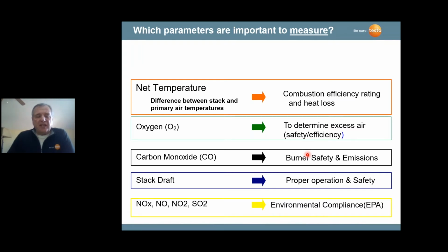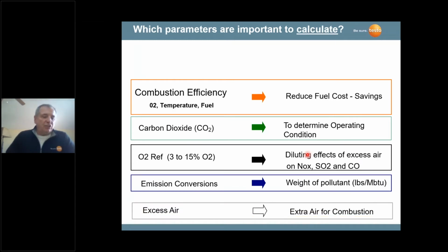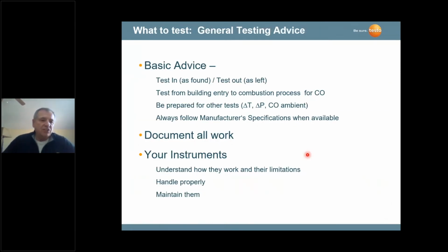Here are the measurements that we measure: net stack temperature, oxygen, carbon monoxide, draft. All these are sensors that go into an analyzer. We do the calculations too. We can measure oxygen and temperature and know the fuel, and we can calculate the combustion efficiency. We can calculate carbon dioxide and other emission values as well. So when using a combustion analyzer, test in, test out. Always check carbon monoxide in the area of the combustion process. Document your work. Most of these instruments today have the capability of Wi-Fi, sending it through the internet, or printing capability. You can print or store information in the instrument.